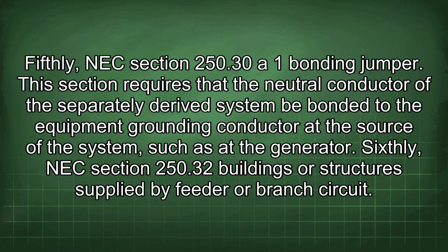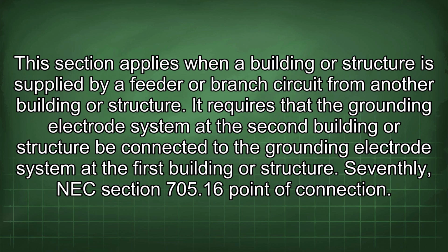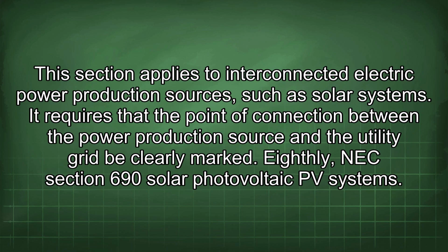Sixthly, NEC Section 250.32 Buildings or structures supplied by a feeder or branch circuit. This section applies when a building or structure is supplied by a feeder or branch circuit from another building or structure. It requires that the grounding electrode system at the second building or structure be connected to the grounding electrode system at the first building or structure. Seventhly, NEC Section 705.16 Point of Connection. This section applies to interconnected electric power production sources, such as solar systems. It requires that the point of connection between the power production source and the utility grid be clearly marked.